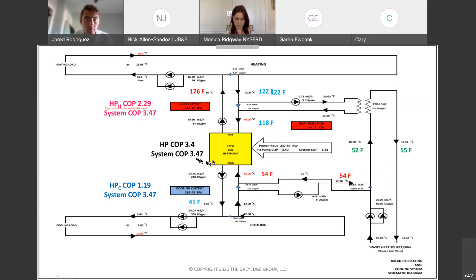You can see our output temperature on the heating side is about 176 degrees. And in this particular example, at the same time, we're making cooling at about 41 Fahrenheit. So this is the chiller range. This is the range we use. This is nothing uncommon. But you'll notice that we have an ambient loop here that we're either drawing from or sinking energy into to help maintain this heat pump at its highest curve. So this is one of the first applications where we can start to look at a practical way to heat and cool a high temperature system. And again, it's going to depend on your distribution system.